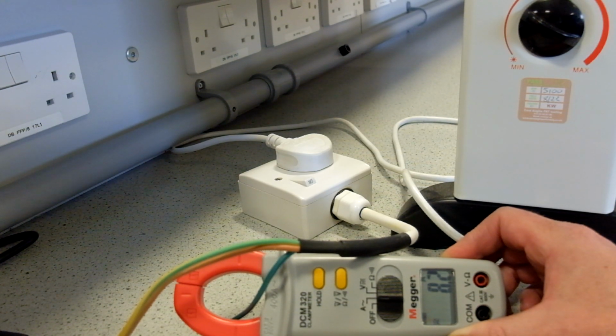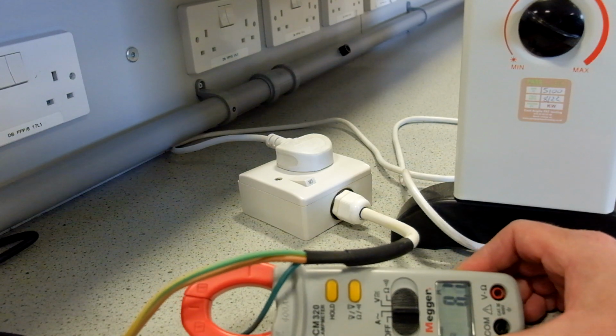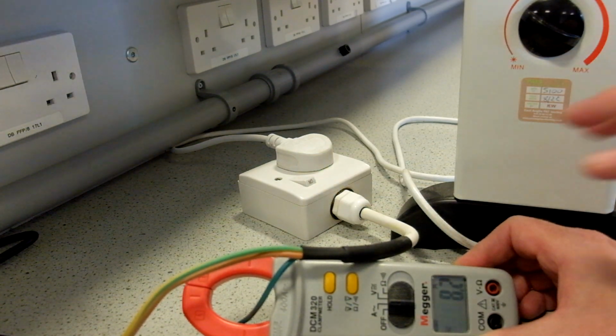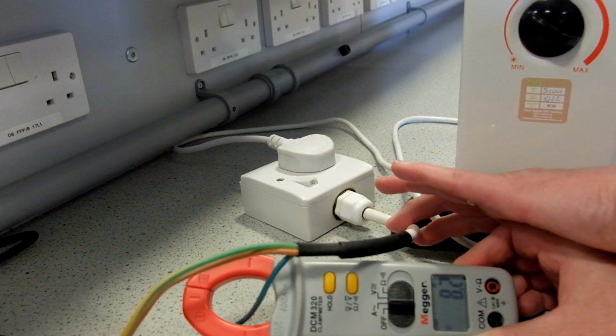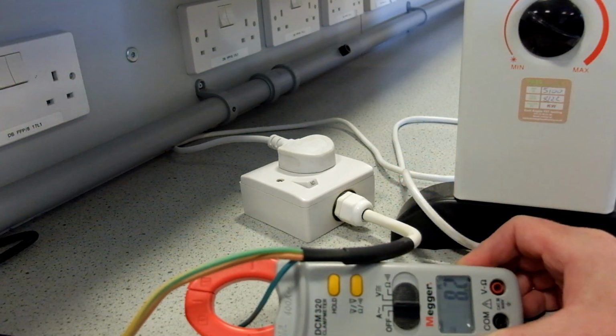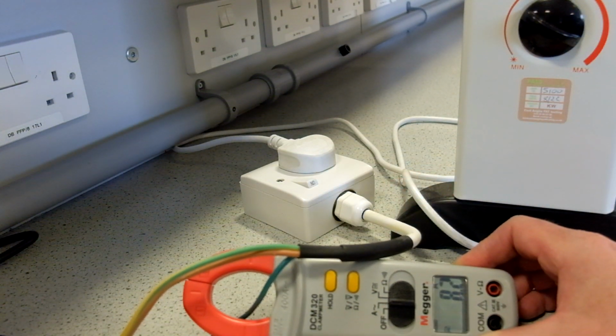So we can measure current, and we're measuring current without breaking into the circuit. So why have we got the single core cables coming out? Normally, double insulated cable for safety. We've taken out the single core so we can measure around each individual wire. We've got neutral at the moment.